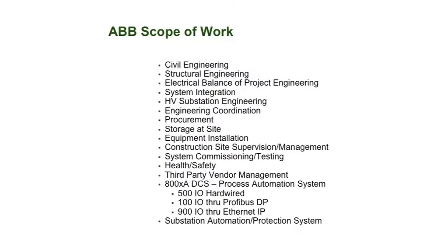The 800xA system was 500 hardwired I/O points, 100 I/O points through Profibus, and 900 I/O points through Ethernet IP. And using Ethernet IP gave us faster communication. All the process equipment was PLC controlled. So talking to the kiln, the grinders, the mills, that all came through Ethernet. So we didn't control that equipment, the PLC controlled the equipment, but we sent the starts, the stops, the change and set point. And that was all done through Ethernet.